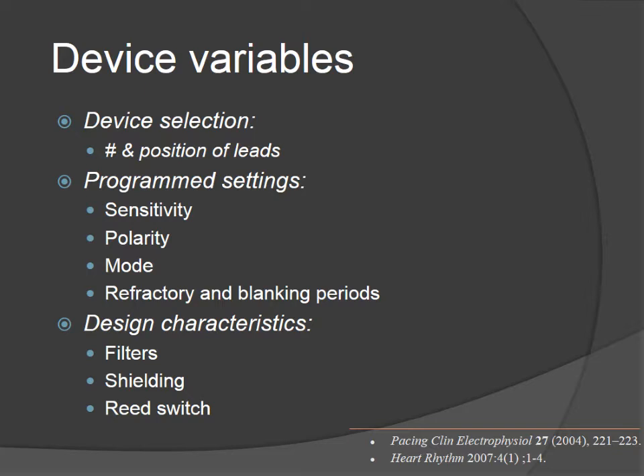From the device itself, there are also a number of variables that affect it: the number and position of the leads, the way we program the device—sensitivity, polarity, the modes we select, how we set up blanking periods and refractory periods—and also the design inherent to the various models, principally the filters, the shielding, and the reed switch, which is the switch that can be affected by a magnet. I mention this not to go through the picky construction details, but so you understand that this is key in the newer MRI-compatible devices, which have gotten rid of this switch that could be affected in the past.